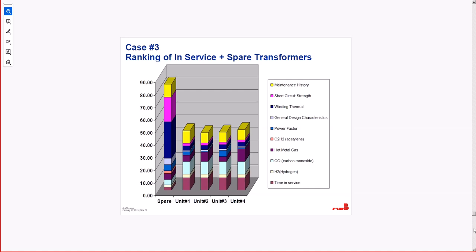Also what we need to take into consideration to clean up the harmonics. Because converters, they always create harmonics. The harmonics in the systems are either created by switching power or by non-linear elements like magnetic core saturation. Those create third harmonic. Okay, ranking of the in-service spare transformers based on all these criteria.